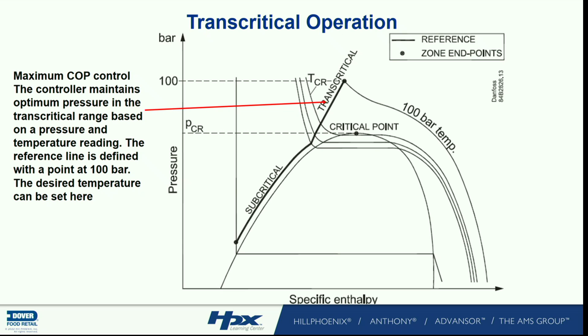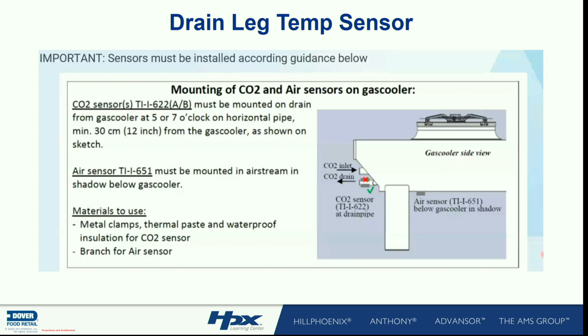All right, remember where we put our sensor. It needs to be not only for fan control, but for the COP control. I need to make sure that drain leg temperature is about 6 to 8 degrees, really 5 to 6 degrees off the gas cooler outlet, at 5 or 7 o'clock. It can't be on the top, it can't be on the bottom. All right, now we look here, we got these rolling, we're doing our thing.